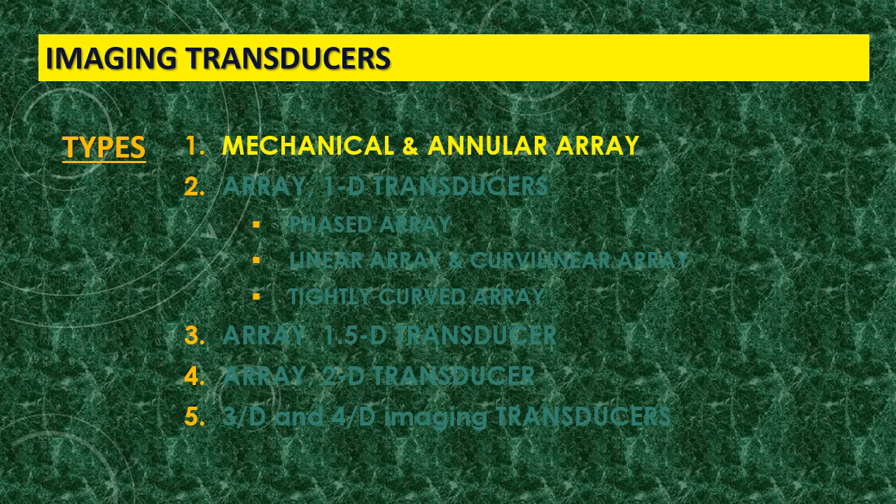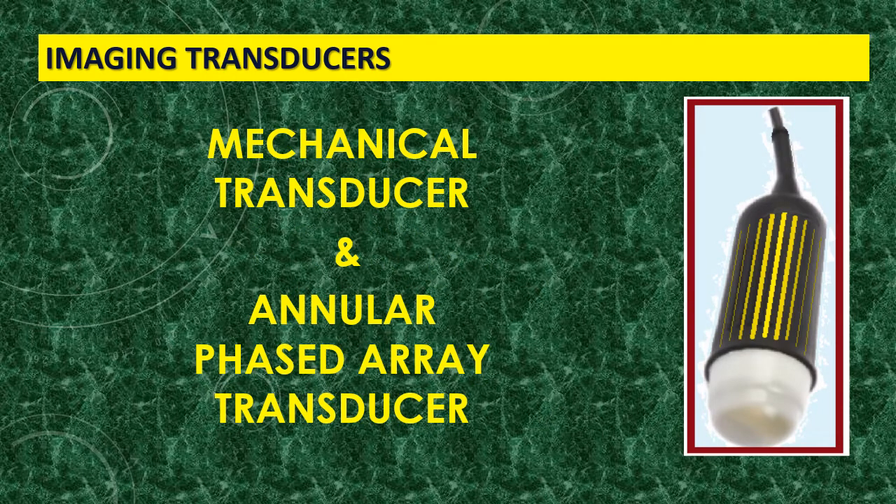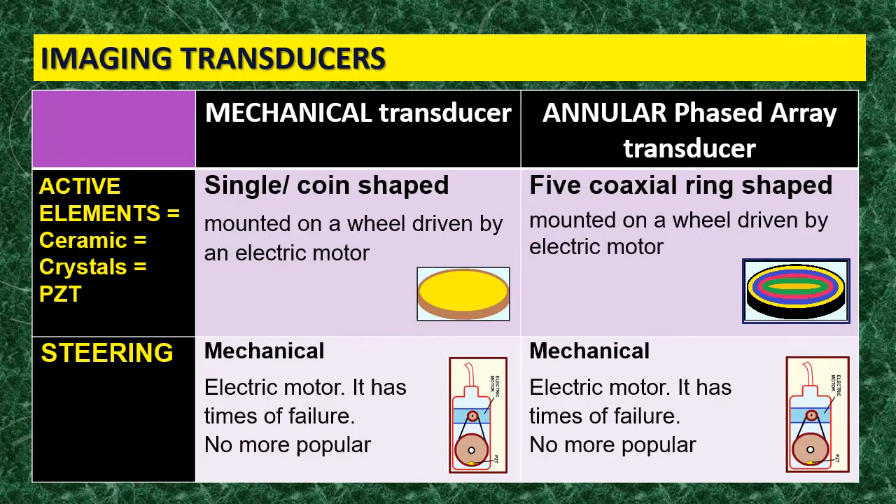We are now discussing the mechanical and the annular array transducers. Why are these two probes grouped together? Because both are steered mechanically, and both are no longer on the market. Why? Because this mechanical steering by the electric motor is subject to many breakdowns, and while you are working the probe can suddenly stop — and that is not a good thing.